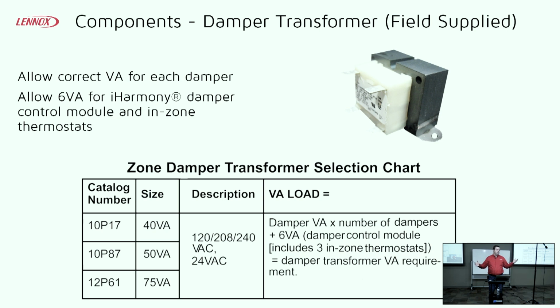If you're doing a 5 VA damper, let's say, and you've got 4 of them, that's 20 watts. So we know that, okay, with that plus the 6 watts from your damper control module and your zone thermostats, that means we need 26 watts. And with a 40 VA, we've got enough capacity.